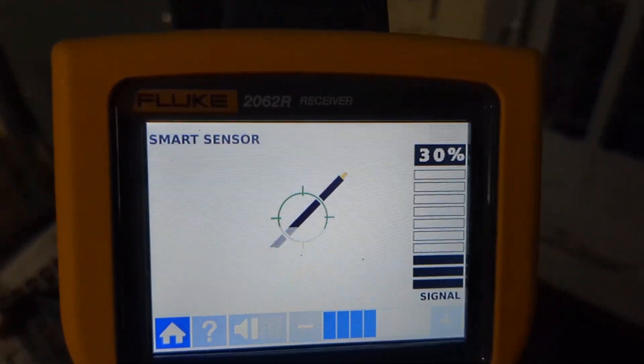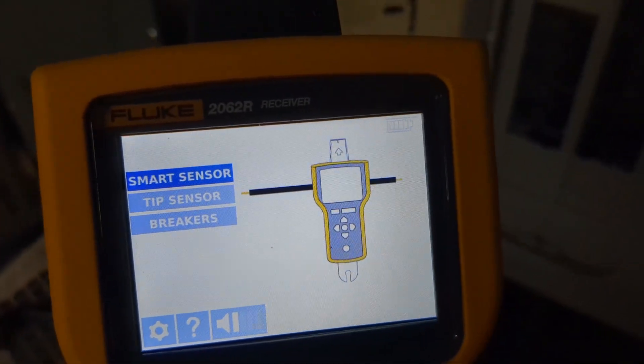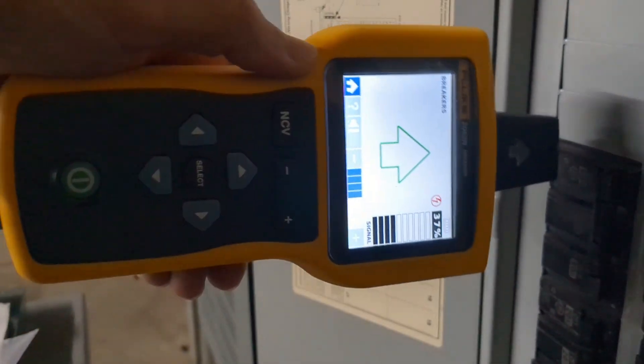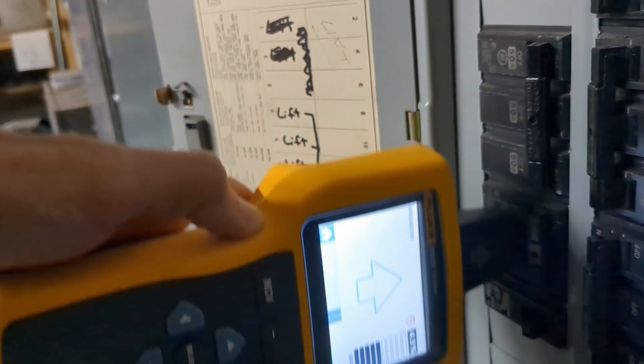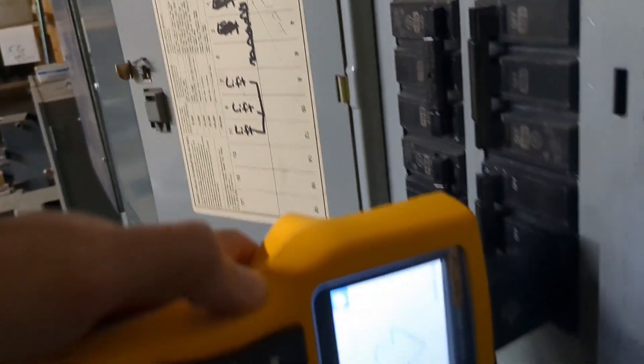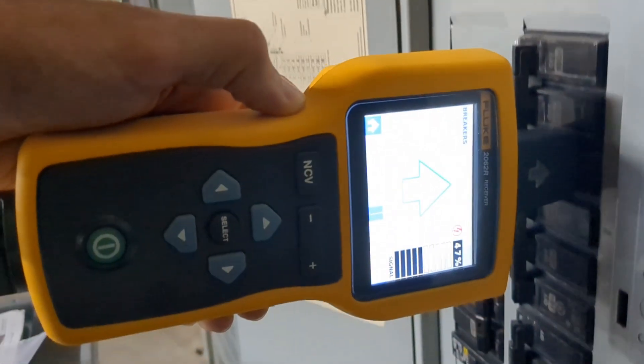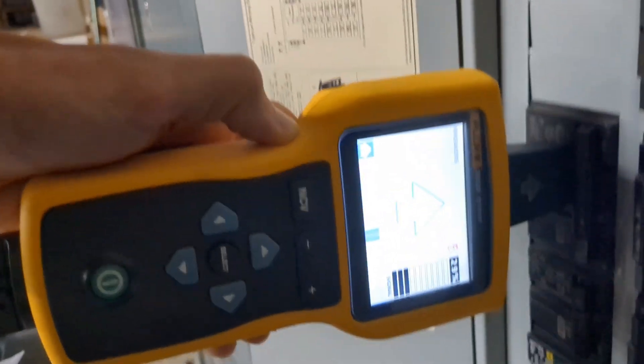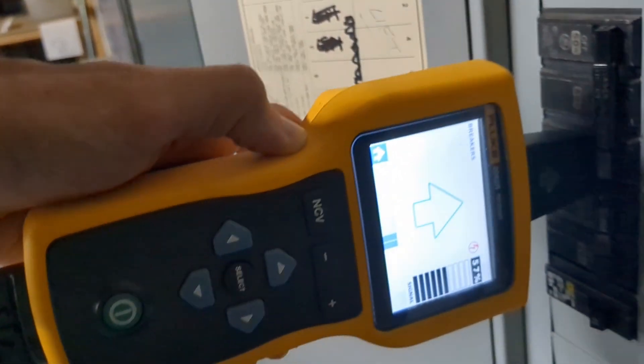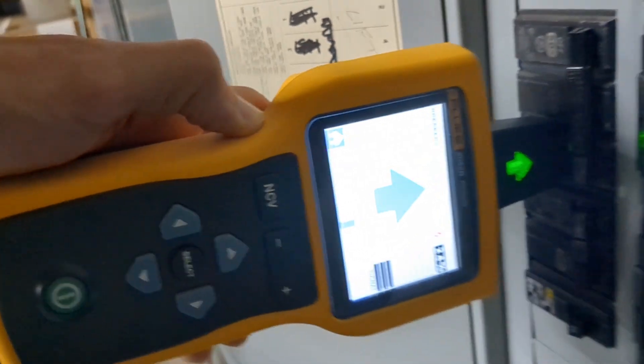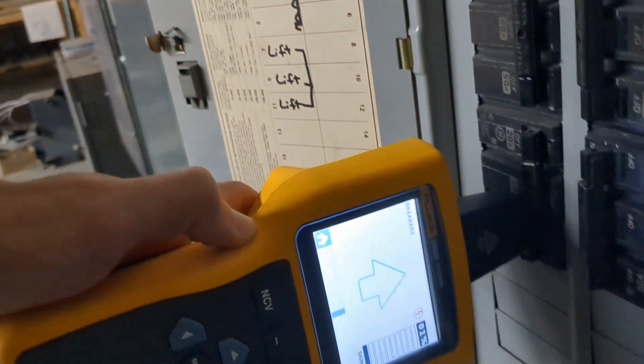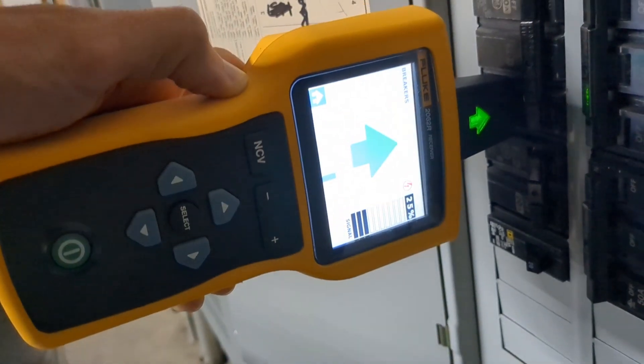We're now going to jump to breaker sensor and we're going to do it at the breaker panel. This is probably 60 to 80 feet away from where we were and we can go down both sides. Once in a while it'll turn green and when we get the green solid arrow that is going to be our breaker and we know which phase it is and which breaker that we need to mess with.